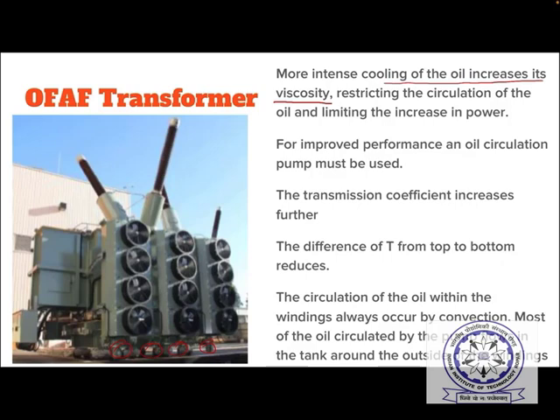Oil viscosity will increase, and this restricts the natural circulation of the oil, limiting the increase in power. Therefore, there is a limit using just fans. Therefore, for improved performance, an oil circulation pump must be used. So these pumps are used in the OF-AF transformer. The transmission coefficient, of course, increases further, and the difference of T from top to bottom reduces.